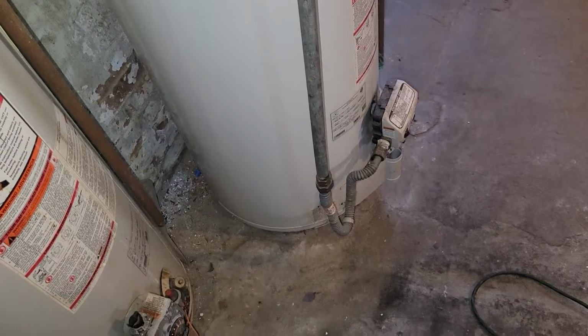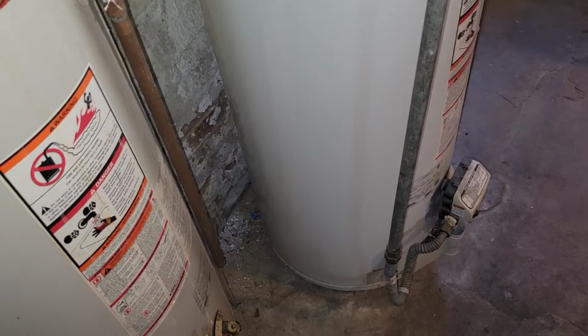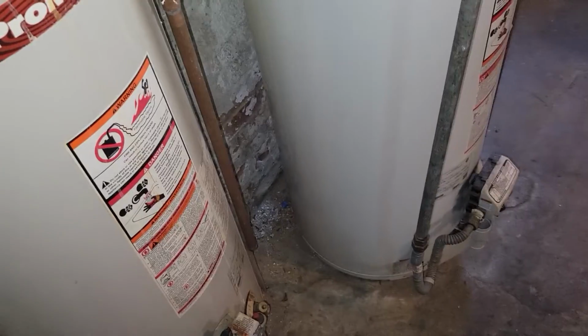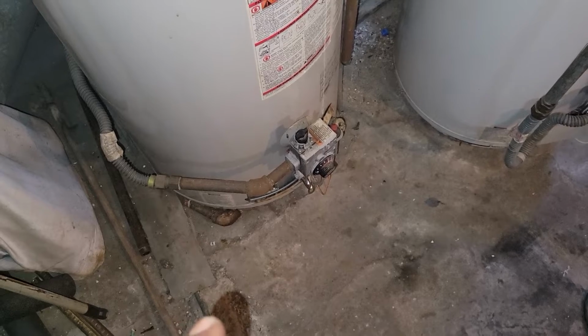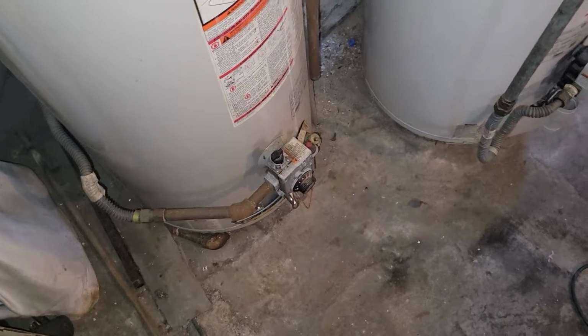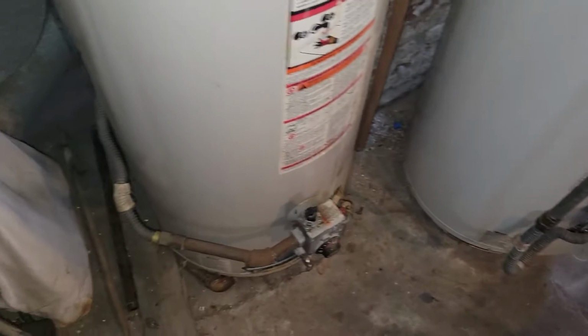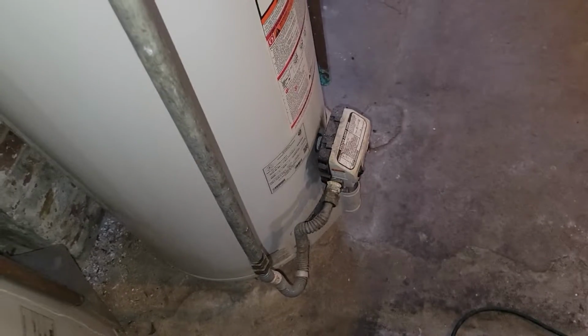And what happens when it does that 90-degree turn, it encourages any junk that's in the gas, debris, coke, to fall out. Again, coke is like a spatter of tar. Imagine tar atomized. And it falls into the bottom of that leg. That's the reason for the dirt leg. If you don't have a dirt leg like this, the junk can get in the valve, and the tolerances where the valve opens and closes are really small. I have actually seen a gas valve go bad because junk came through the natural gas line and got caught in it. It's like a solenoid with a plunger, but the clearances are really tight in there. So you can get a grain of sand or a piece of dirt or coke, which is tar, in that valve and the party's over.